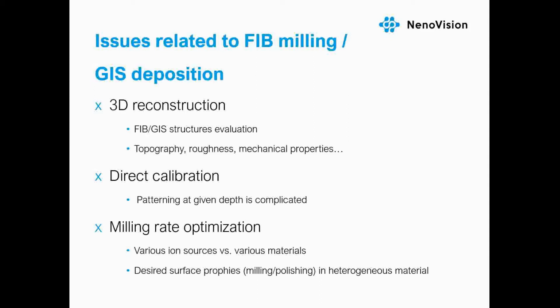The multimodal analysis using an addition of high vacuum compatible AFM can eliminate the already mentioned limitations, but also enables to combine the capabilities of all three systems. And this combination opens up the possibilities of sample analysis that were not possible by separate AFM and FIB-SEM systems. Let's have a look at the main LiteScope benefits for focused ion beam applications.